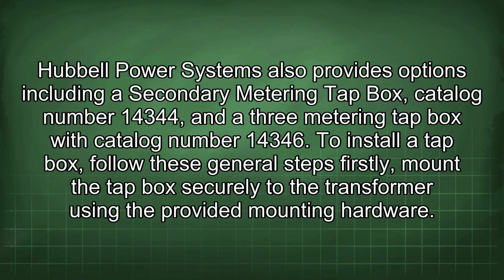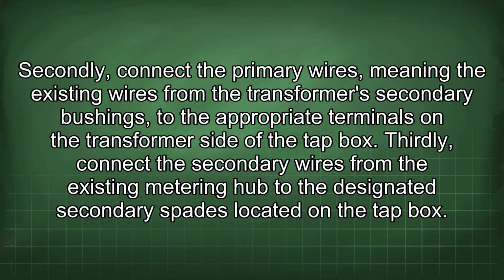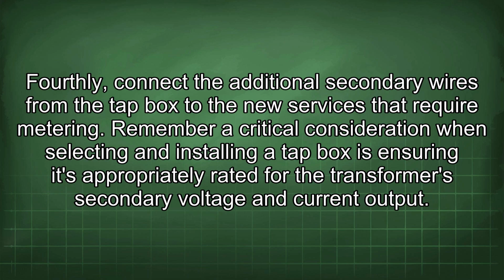Firstly, mount the tap box securely to the transformer using the provided mounting hardware. Secondly, connect the primary wires, meaning the existing wires from the transformer's secondary bushings, to the appropriate terminals on the transformer side of the tap box. Thirdly, connect the secondary wires from the existing metering hub to the designated secondary spades located on the tap box. Fourthly, connect the additional secondary wires from the tap box to the new services that require metering.